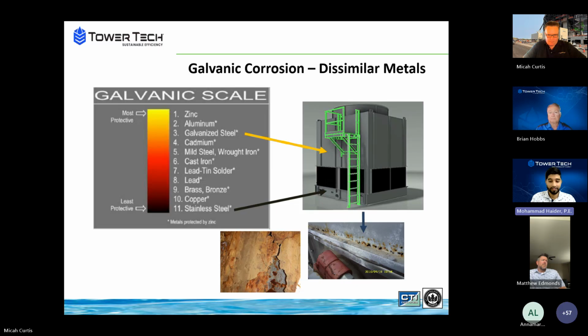And the interesting thing about scale and corrosion is that they don't just coexist with the actual bacteria. They actively create and protect an environment that allows the Legionella bacteria to grow. And that environment is created by scale and corrosion. So you really want to fight scale and corrosion. As you can imagine, rough surfaces in general create attachment sites for the bacteria. If you have a very smooth, polished and clean surface, the bacteria is not going to be able to attach or have an attachment site.